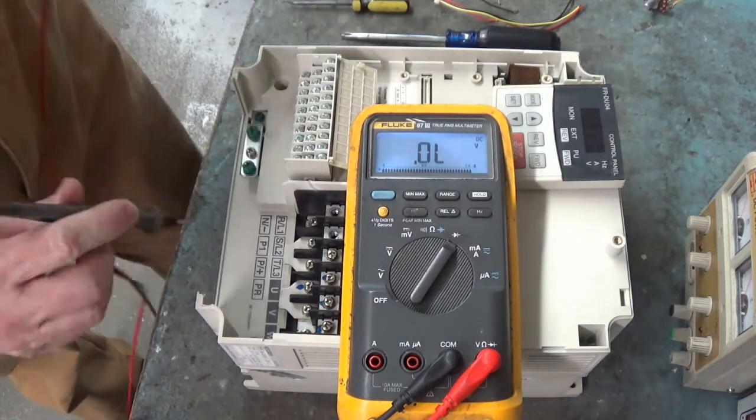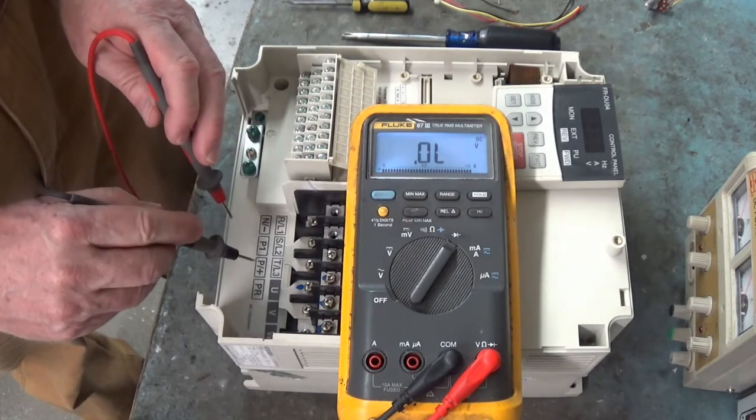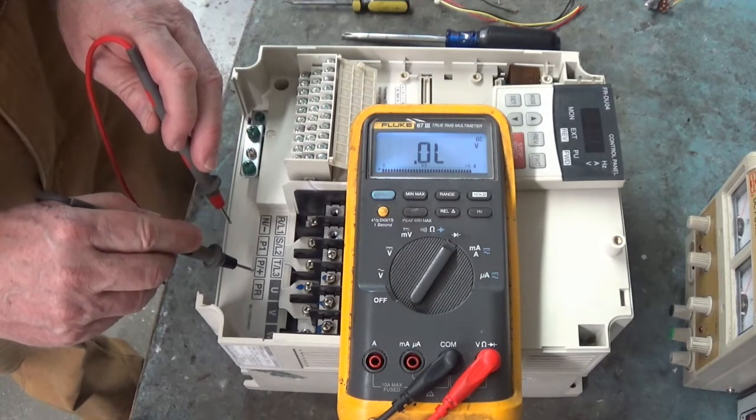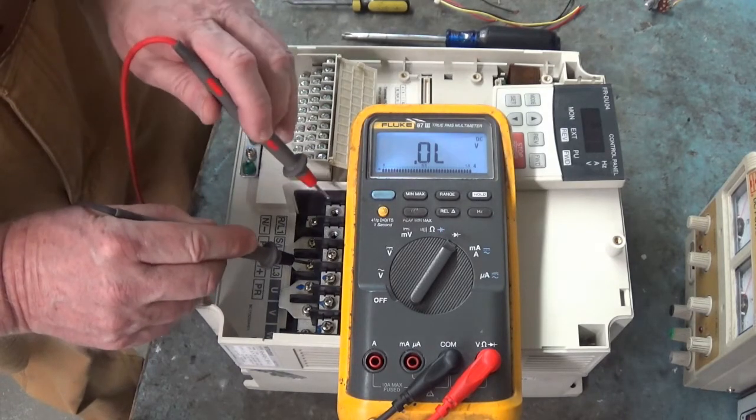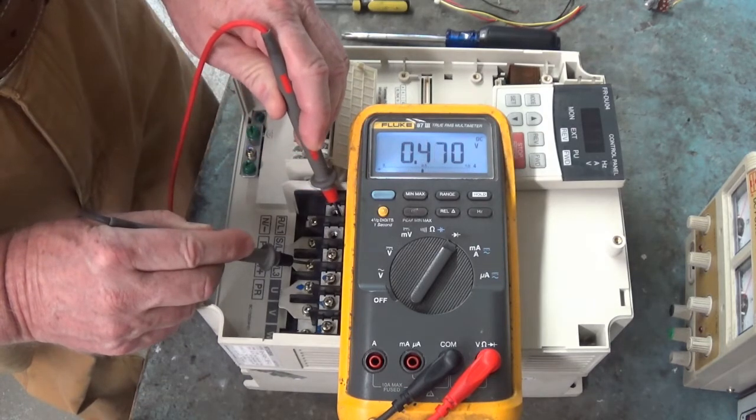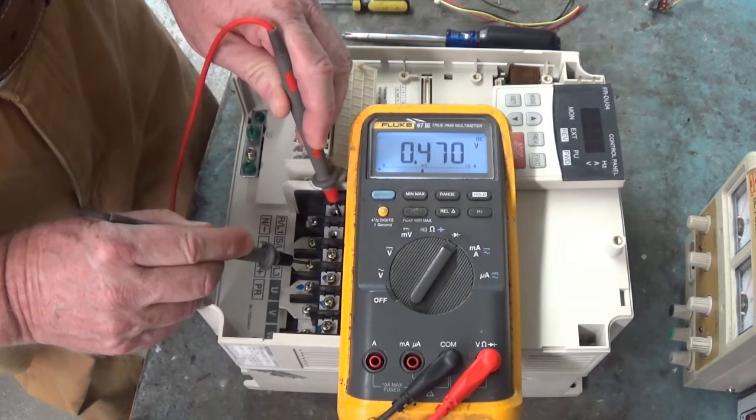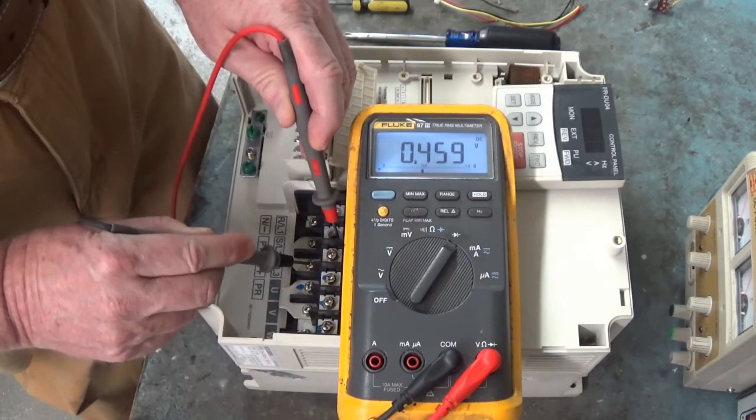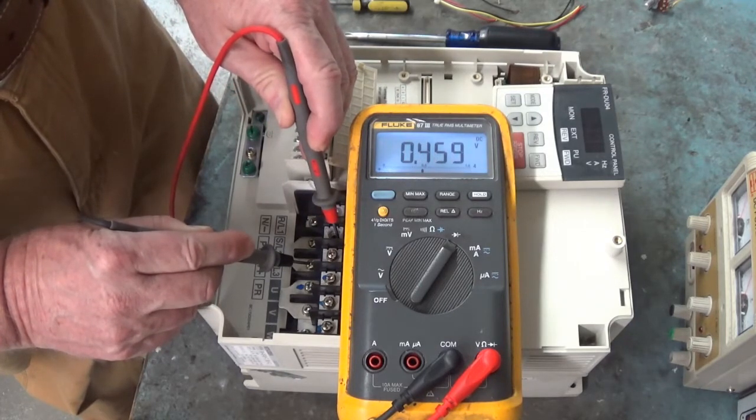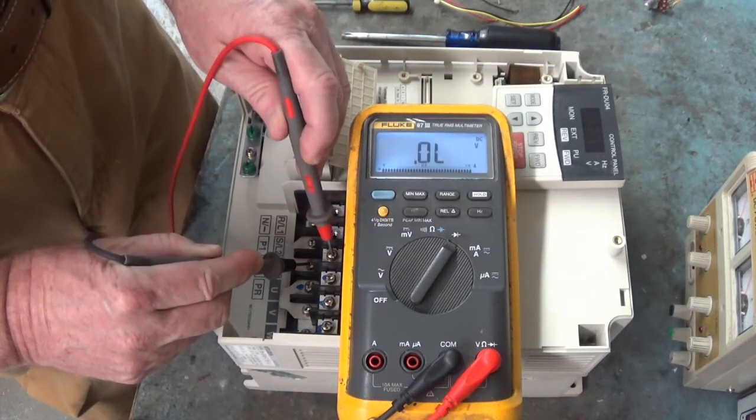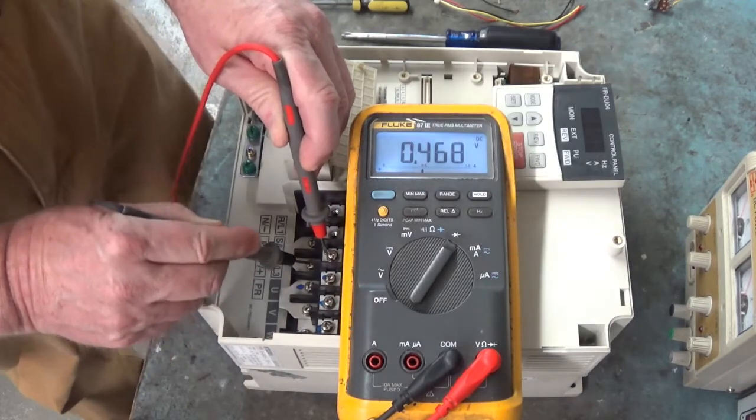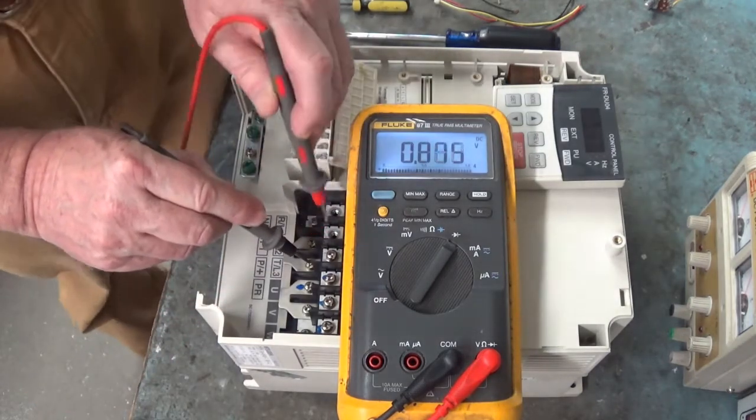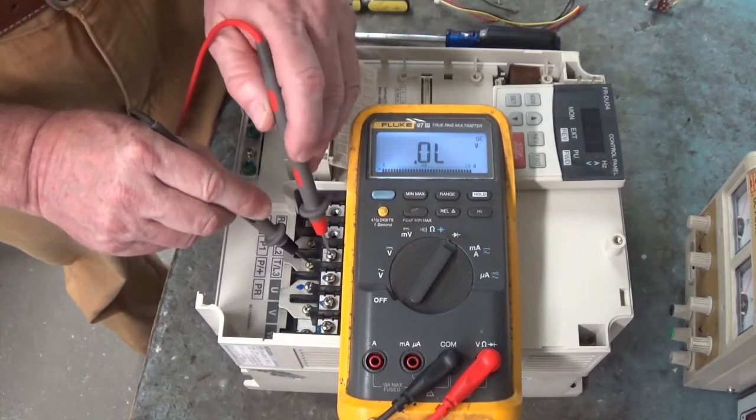Now let's reverse leads. We're going to put the black lead on P slash plus and P1. That's our bus plus. And a red lead on R slash L1. 0.470. Red lead to S slash L2. 0.459. Red lead to T slash L3. 0.468. So our three-phase bridge has good diode drops.